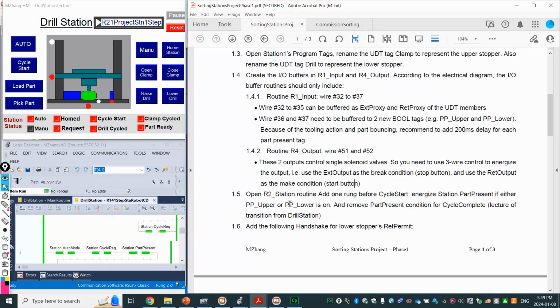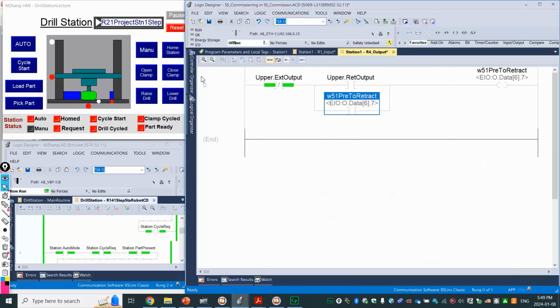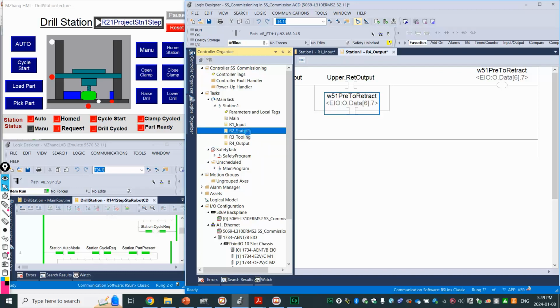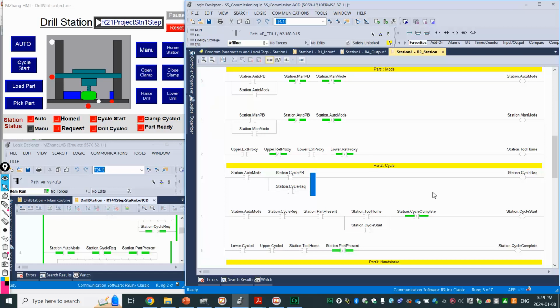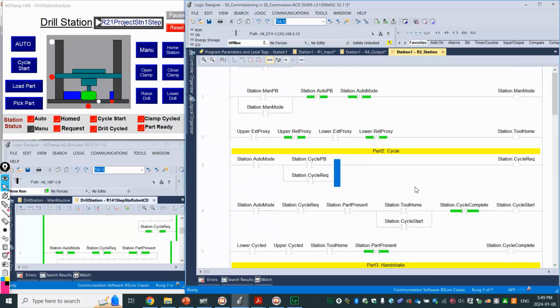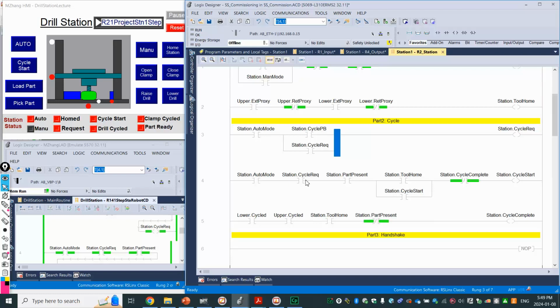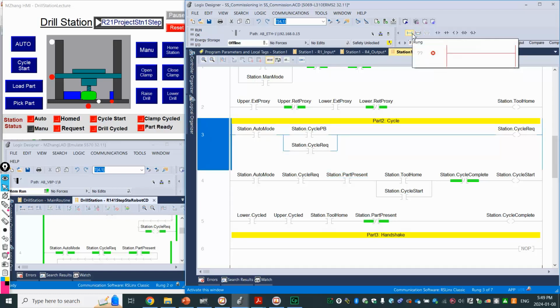So, on the R2 station routine, add one rung before cycle start, energize the station part present if either is on, and remove the part present condition for the cycle complete. Okay, so that's the other thing. Remember, this is not exactly the same as the drill station, so that's why we need to do some modifications on that. All right. So of course, over here, part present. Yeah, part present. So on the drill station, you can see that's the part present. But on our sorting station, especially on station 1, right?